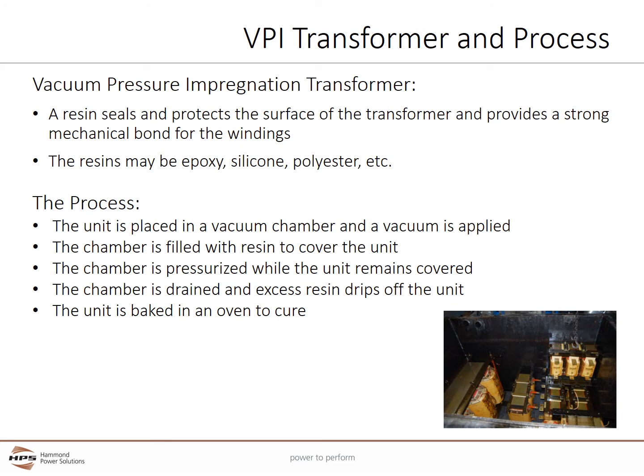Vacuum pressure impregnation or VPI transformers are common in North America. A resin completely seals or protects the surface of the transformer and provides a strong mechanical bond for the windings. The resins have many formulations and may be epoxy, silicone, polyester, or other materials. This varies from manufacturer to manufacturer.